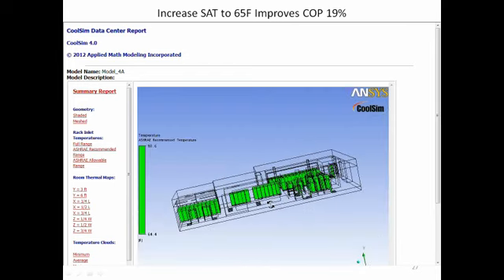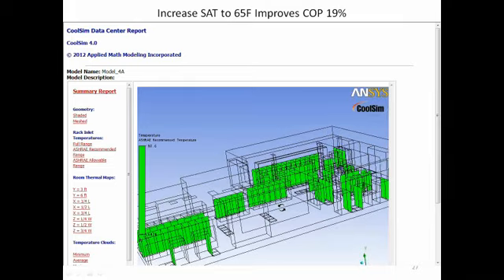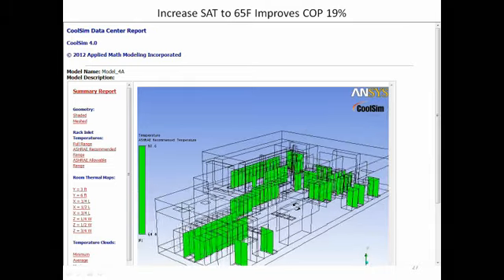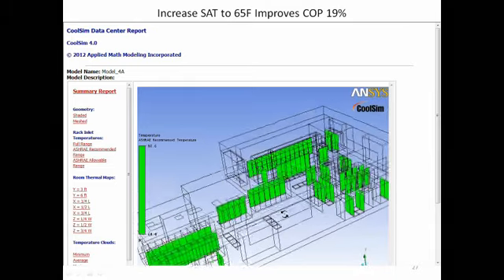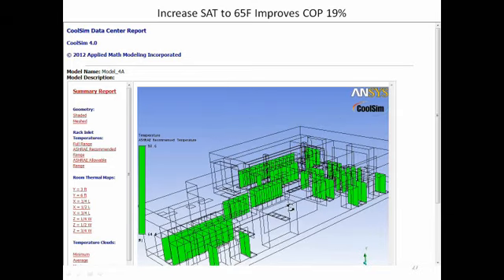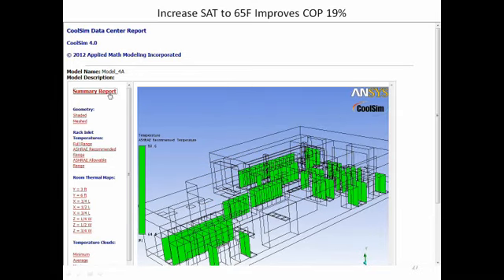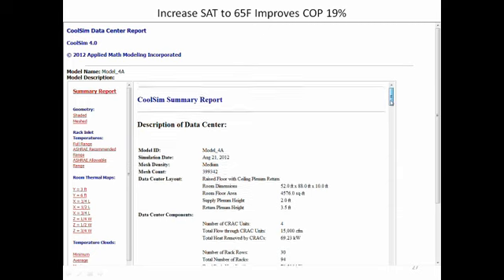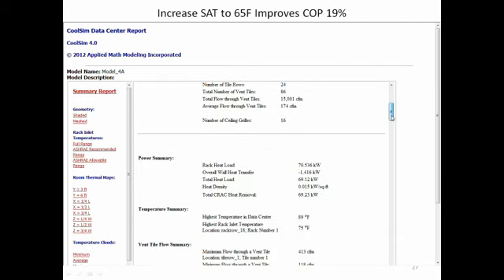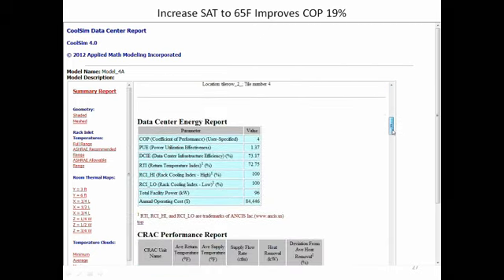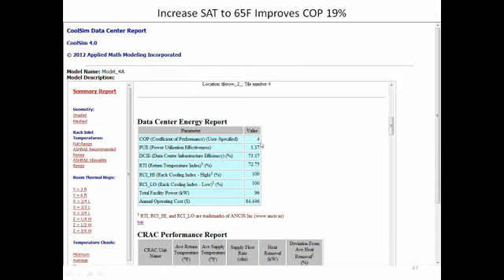And you see it's all green. So we're doing much better. Now we've got the racks in compliance. They're all in compliance. We're operating the set point at 65 degrees of supply air. We've got one CRAC unit on. Now many of you will say, and look at the COP now at 4.